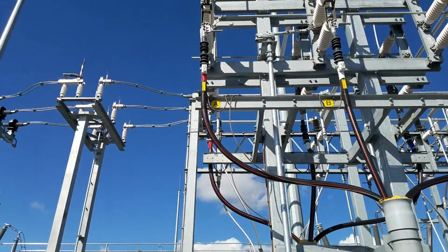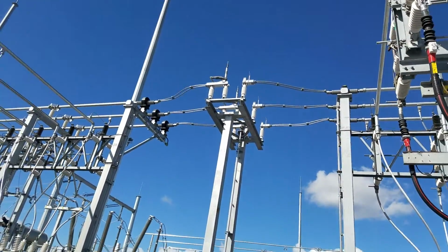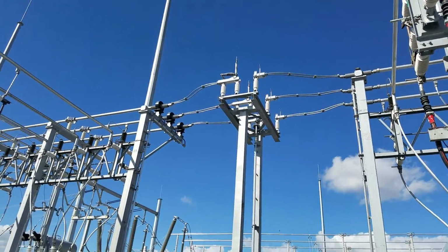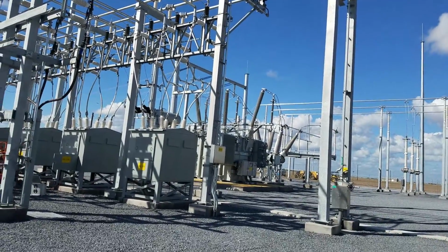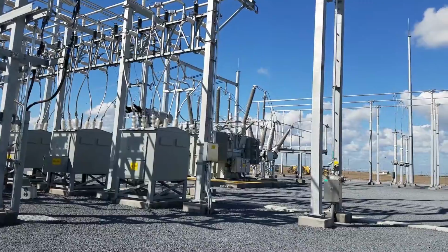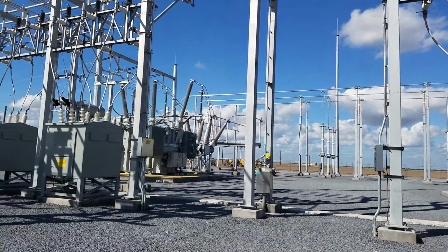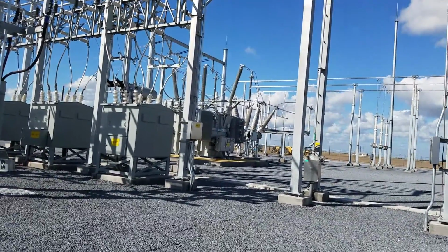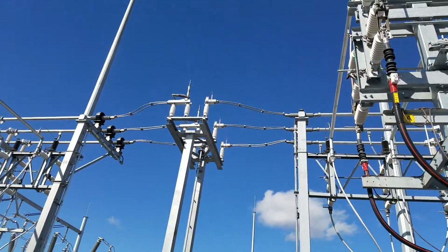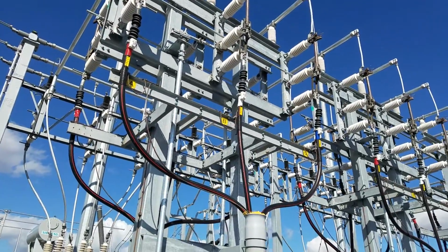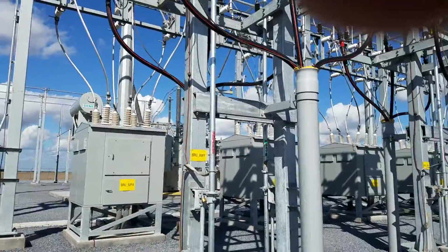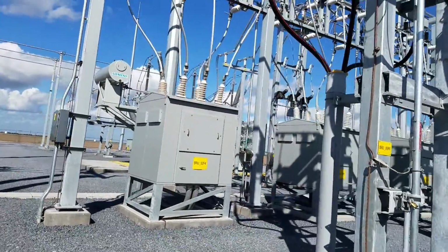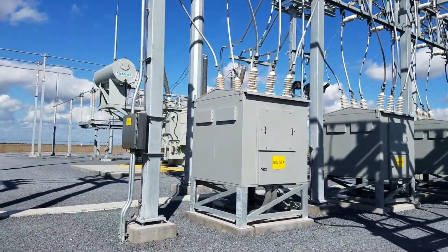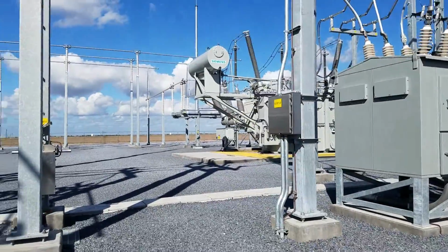And then they have a tie switch here in the middle of the 2 bays, and what that allows you to do is, say one transformer is down for maintenance or has issues. Say the breaker has issues on one bay, you can close that switch and you can feed power through and over to the other bay, and then through this transformer. So it's basically to keep things online if you have any maintenance issues.